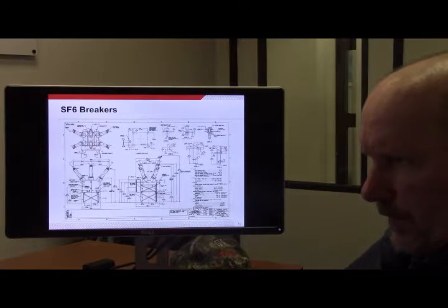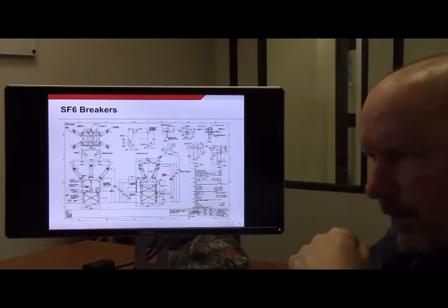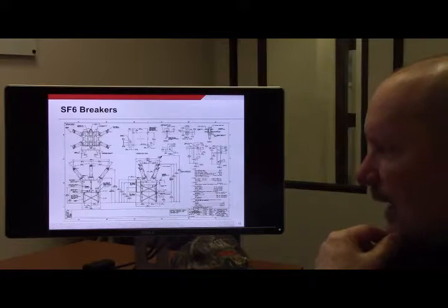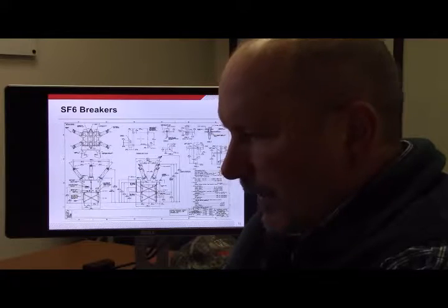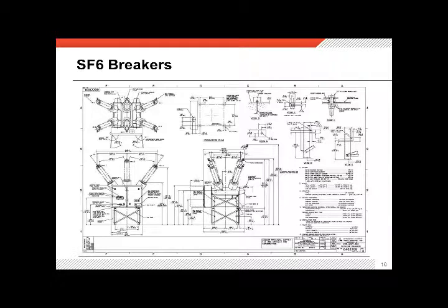Anyhow, I want you to now go to this drawing. It's one of the handouts that you should have in your package and that you had for this presentation. Now, this is an outline drawing for a circuit breaker. Really kind of an interesting thing. And you'll always have one of these with a circuit breaker, and there's a lot of interesting information that you need for both the physical design of the circuit breaker, but also the wiring of it too. I'll show you what I mean.